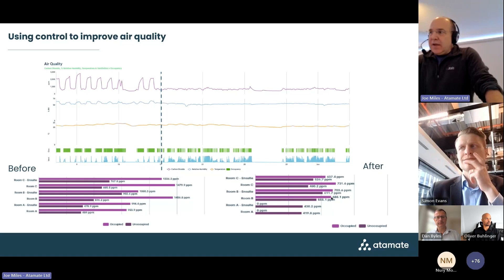Then we turn on the ventilation controls based on carbon dioxide levels, so we're now controlling the air quality in that space. As you can see, the air quality smooths out enormously. There's still occupancy in the space, so the reason it's smoothed out is not because there's no one in the room. You can see the fan is going on a lot more often, and the air quality has improved. It's now averaging, for people who can't see it, around 600 to 700 parts per million occupied, so we're down at around 680 parts per million. That's a significant improvement in the space.